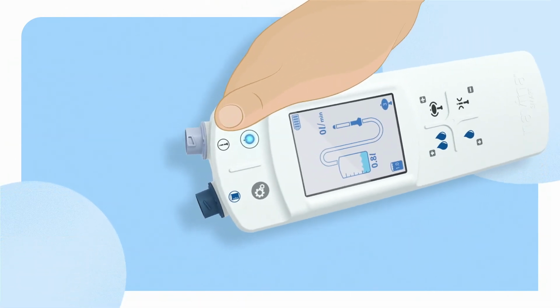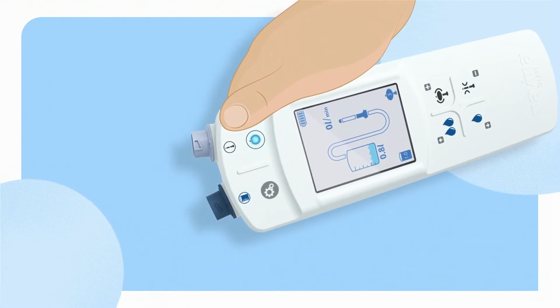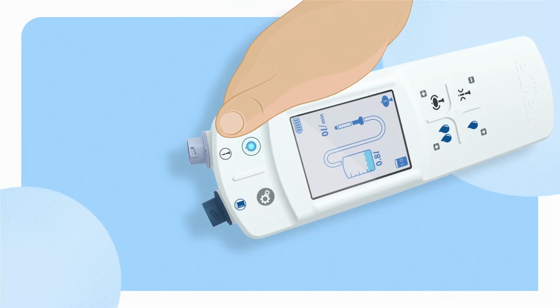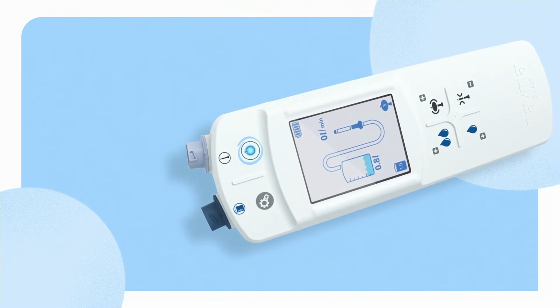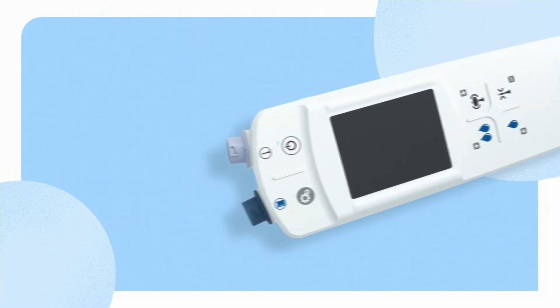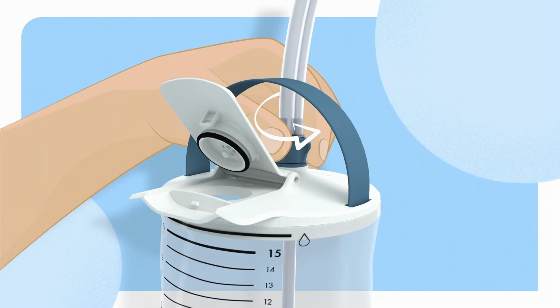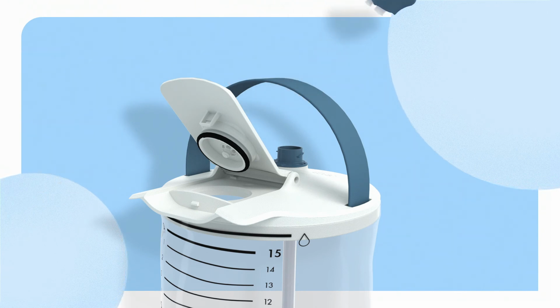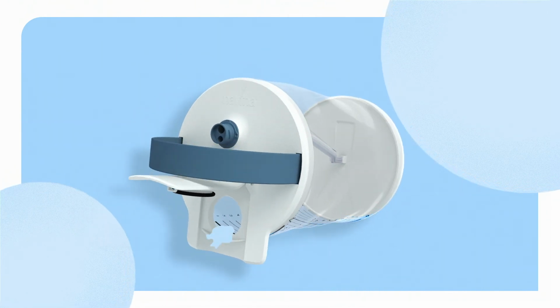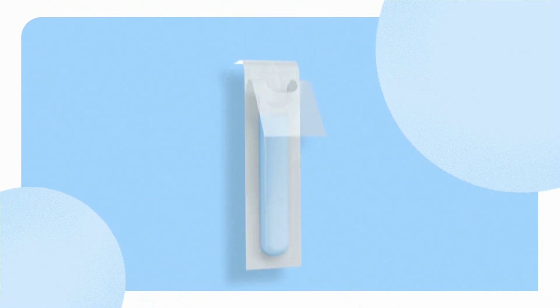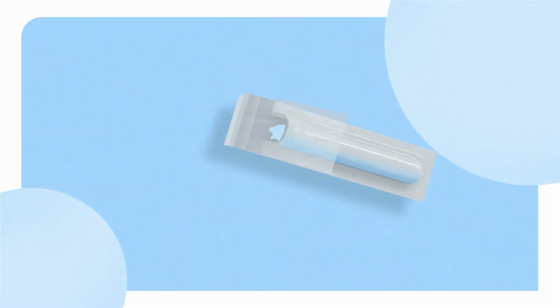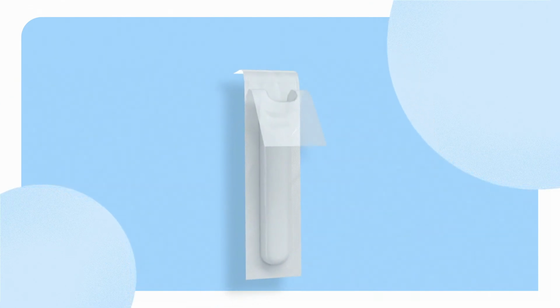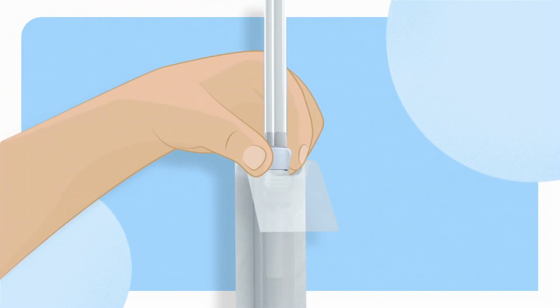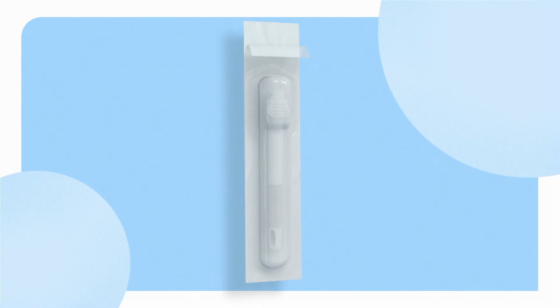Once the tubes are removed, turn the unit upside down into the toilet or sink to empty any remaining water left in it and then turn off the control unit. Next, we have the water container. Remove the dark blue connection from the water container and empty the remaining water. Lastly, we have the rectal catheter. Empty the catheter package from water. Holding the tube with the white connection, place the catheter back into the package. Now, disconnect the rectal catheter from the tube and dispose of it with its package with household waste.